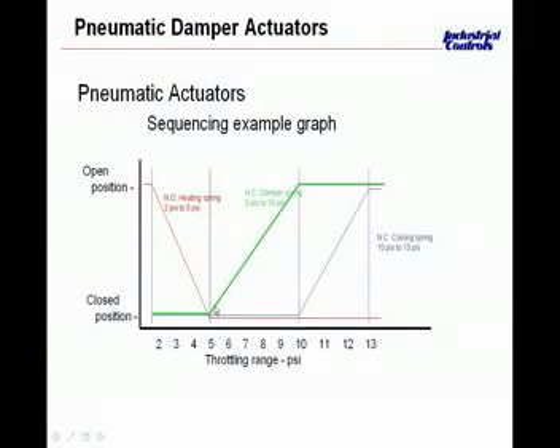So as the space temperature in that application began to rise, our heating valve would close. And on a continued rise in temperature now, instead of operating the chilled water valve as we did before, we'd now start to open our economizer dampers to the outside. Our cool, fresh outside air would come in and start to cool the space down. If the air wasn't sufficiently cool or the space load was too high, the temperature in the space would continue to rise and our thermostat branch pressure would continue to rise, at which point our cooling valve would now begin to open at about 10 or so pounds. So you can see here how the spring ranges, again, are so important in sequencing the different products so that they all operate together to achieve your final control sequence.